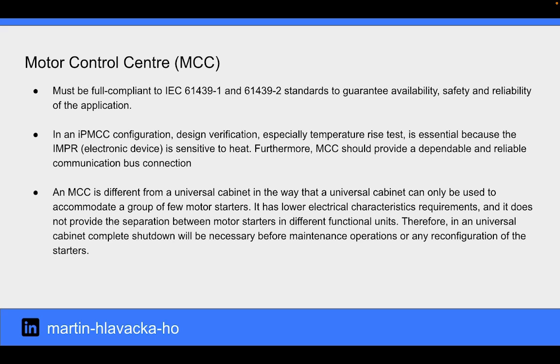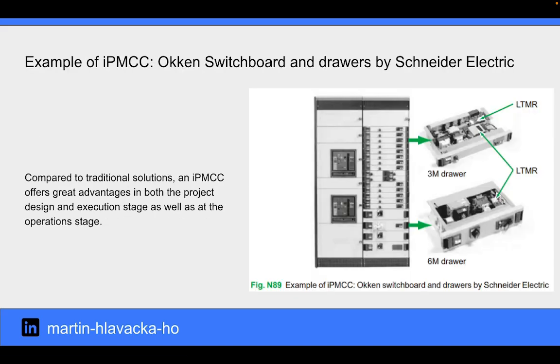An MCC is different from a universal cabinet in the way that the universal cabinet can only be used to accommodate a group of few motor starters. It has lower electrical characteristics requirements, and it does not provide the separation between motor starters in different functional units. Therefore, in a universal cabinet, complete shutdown will be necessary before maintenance operations or any reconfiguration of the starters. On the image, you can see an Okken switchboard and drawers of Schneider Electric.